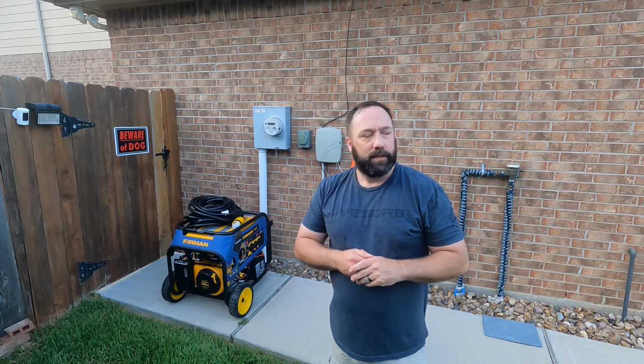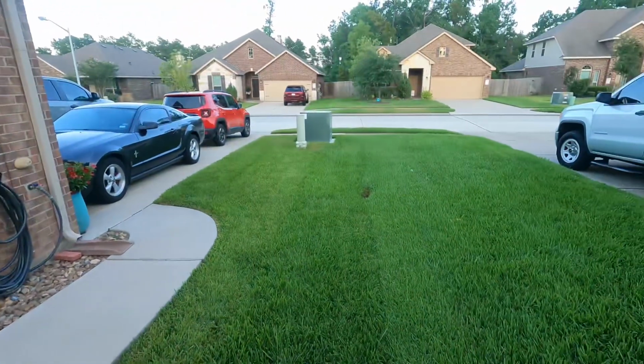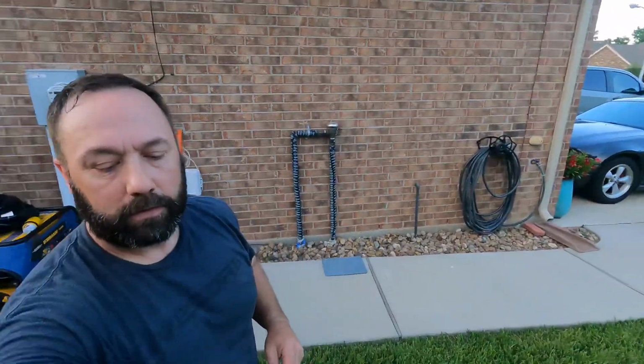You're not putting them in danger like some people do by backfeeding. One, it's illegal, and two, once it hits the pad mount transformer right over here, the 240 volts that you are generating turns into 7,200 volts out on the line. It's a huge issue for the linemen trying to get the power back on, and something we definitely don't want to do.